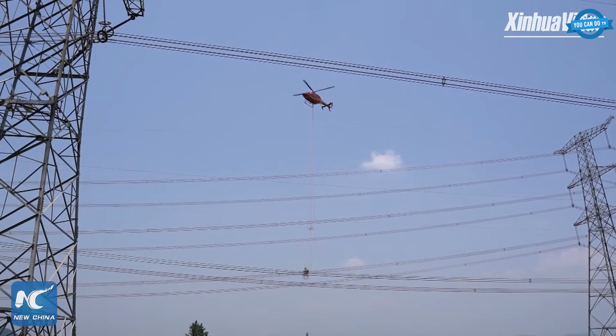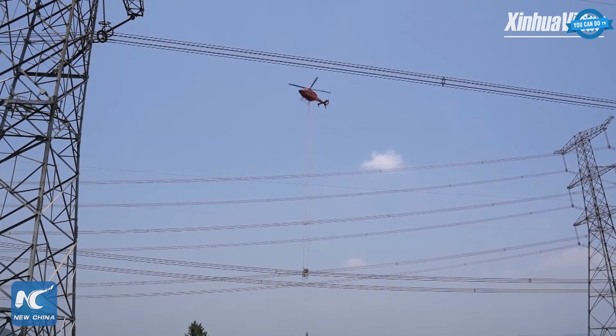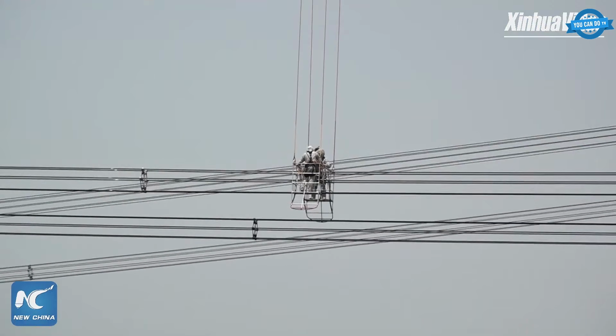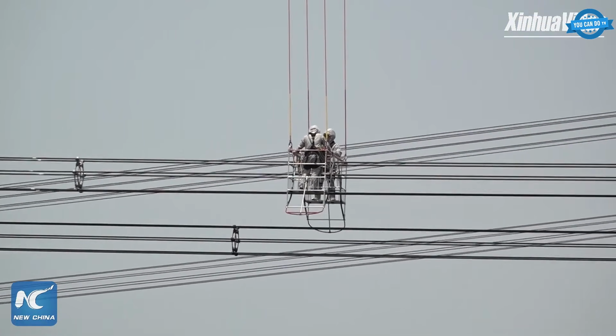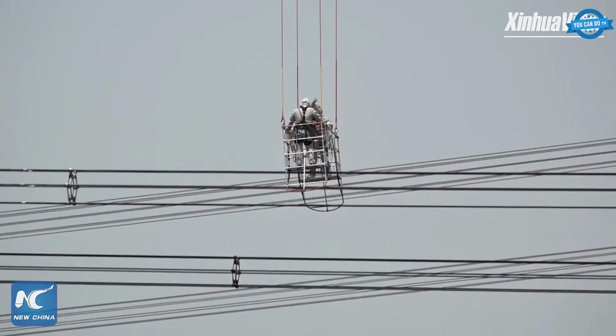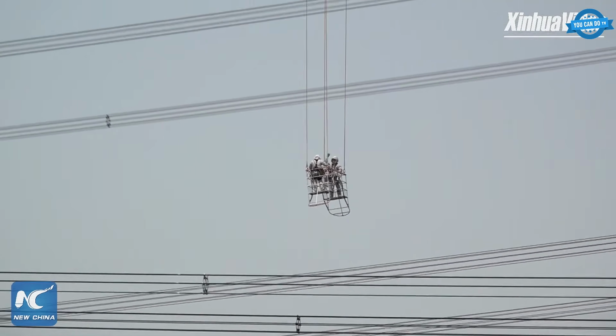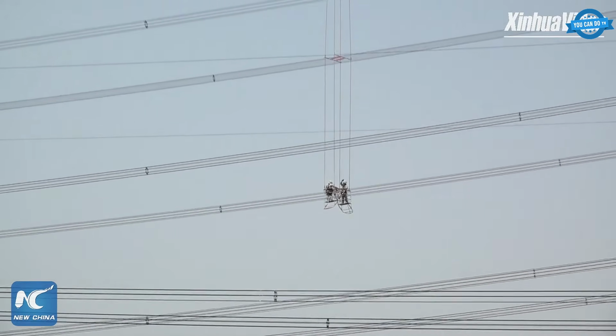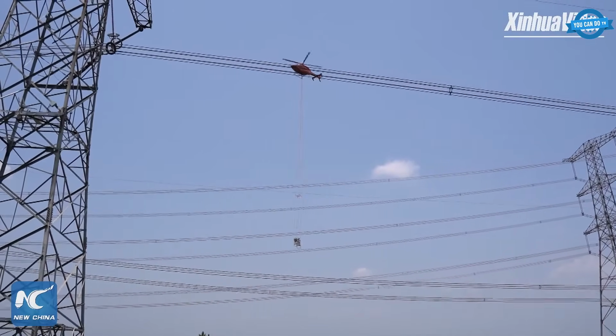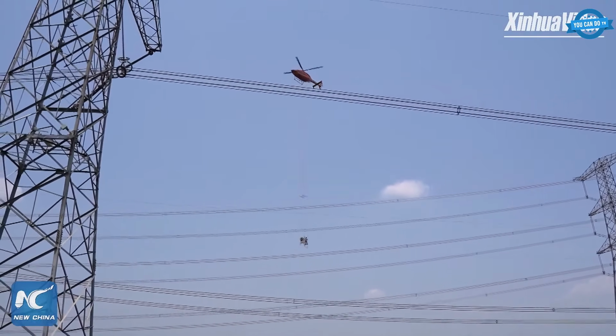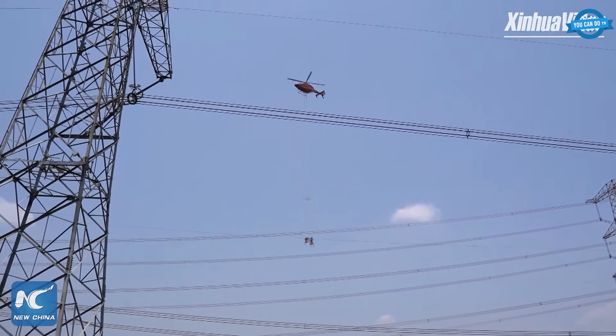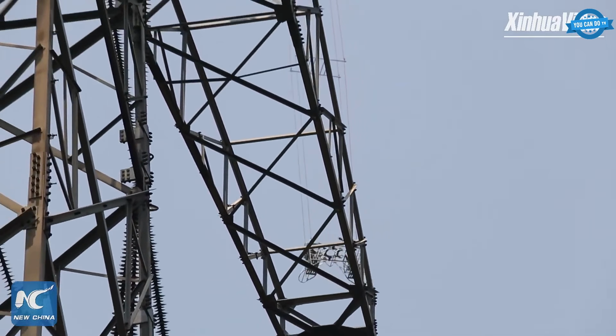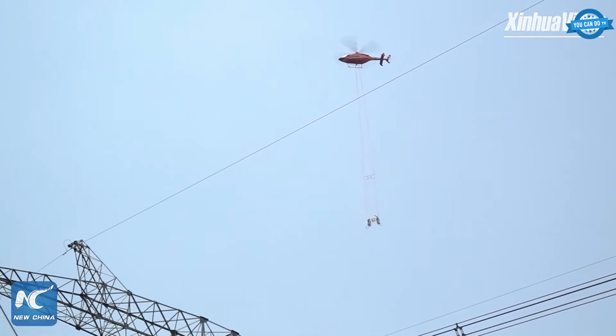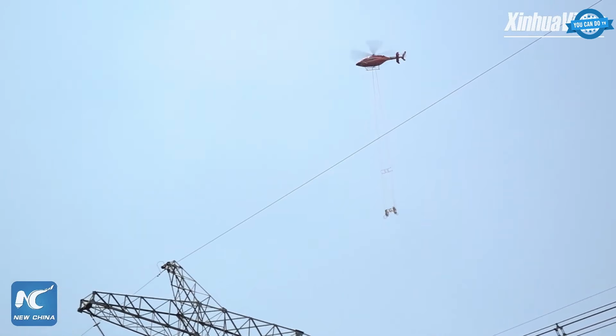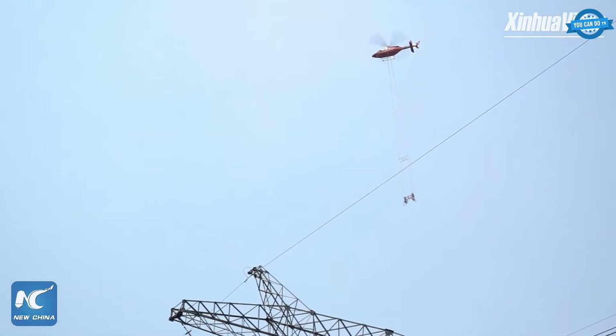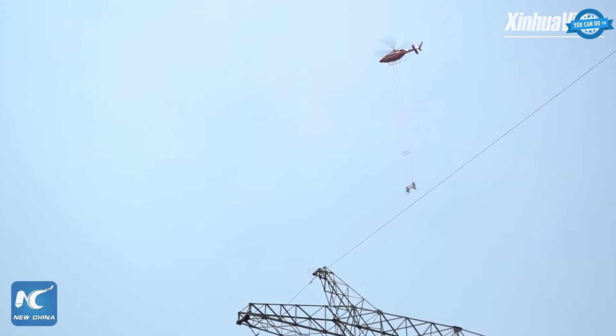The shielding clothing is 75% Nomex and 25% stainless steel fiber, a wearable Faraday cage that diverts the electric field around the body. Helicopter live-line maintenance increases work efficiency 75% over traditional methods and cuts outage duration by at least 5 hours per defect. The 2 linemen and the helicopter crew communicate continuously, adjusting position in real time across narrow spacing between parallel lines.